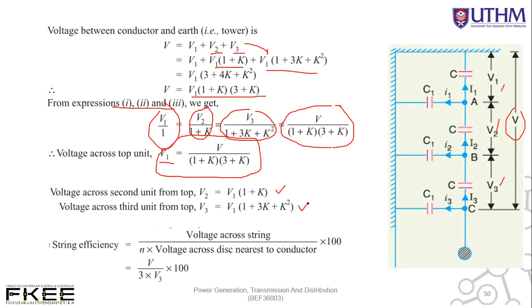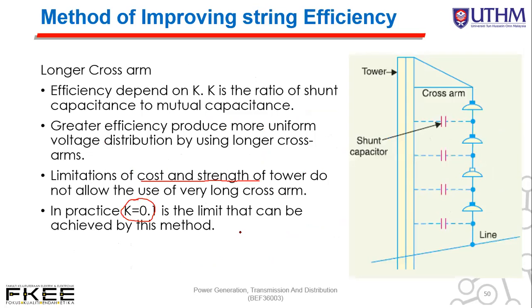All right. Finally, the string efficiency is nothing but voltage across string, which is V, divided by N times the voltage across the unit nearest to the conductor. N is the number of units, and we have 3 units here. Voltage across the unit nearest to the conductor is V3. If we have all these values, then we can calculate the string efficiency.